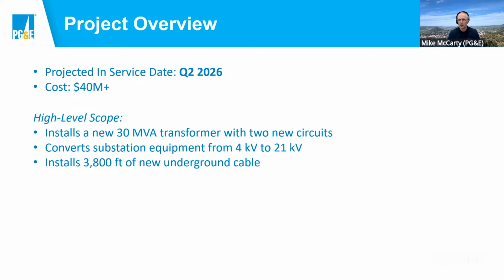To do that and bring this substation in line with our modern distribution standards, we had to start by installing distribution equipment to take on that 4 kV in the interim while we basically decommissioned the substation. We had to do work to reconfigure our transmission system such that we could do the work inside the substation. So that's how this project started. And then once we were able to effectively clear and decommission the substation, it allowed us to go in there and replace a lot of the equipment and bring it up to those new standards, bring in the new transformer, pull in the new feeders, and the new 21 kV switchgear associated with that. So the end result is an increase to the electric distribution capacity in this area. We're bringing on more capacity into the area and an increase in reliability both on our distribution system and our transmission system in this area.